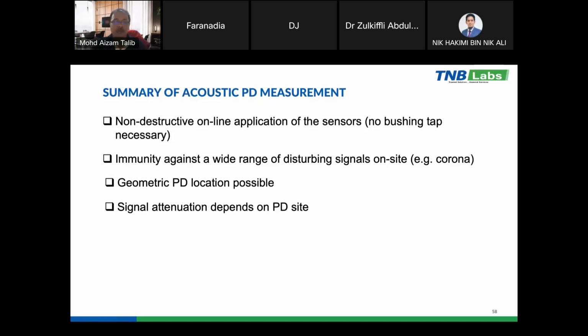Sometimes it is quite difficult to pinpoint, because if the fault occurs at the inner winding, for example at the LV winding and core, the signal needs to travel from the source to the tank of the transformer. There are a lot of barriers, spacers and pressboard, so the signal becomes weak, and finally it is not able to reach the sensor. Sometimes we know there is a fault in the transformer, but due to the limitation of signal attenuation, we are unable to locate the faults.